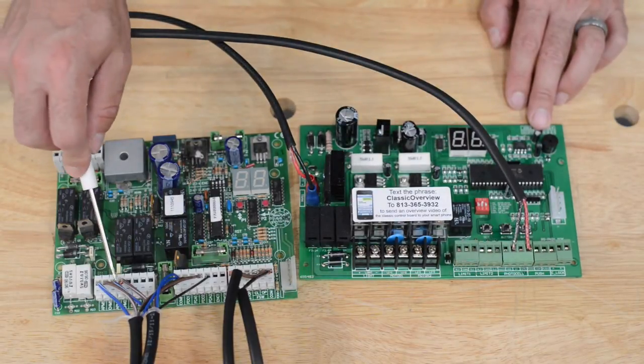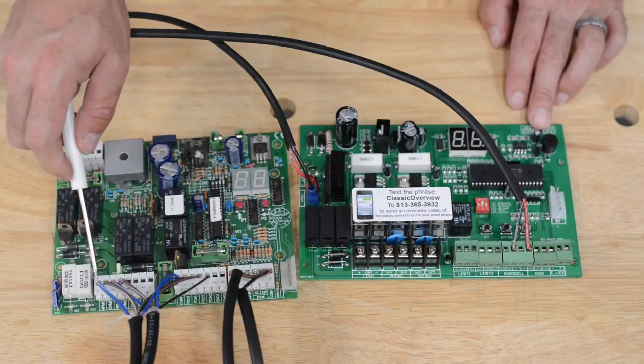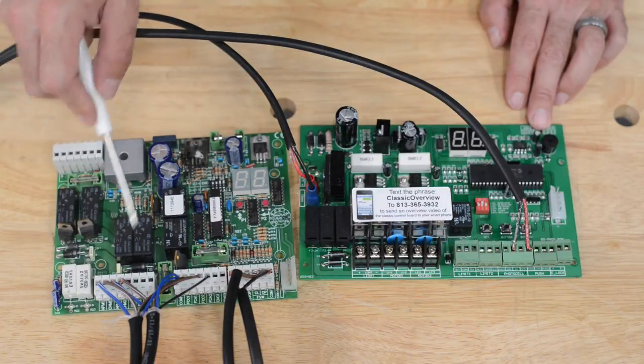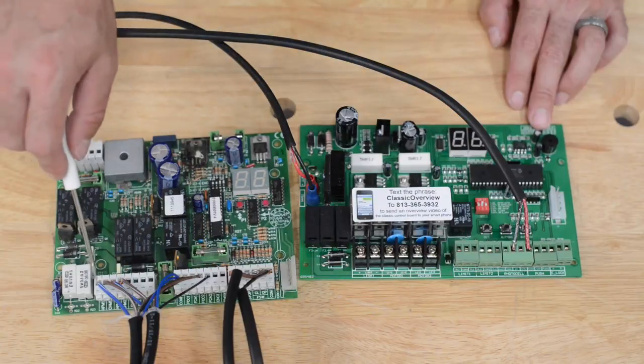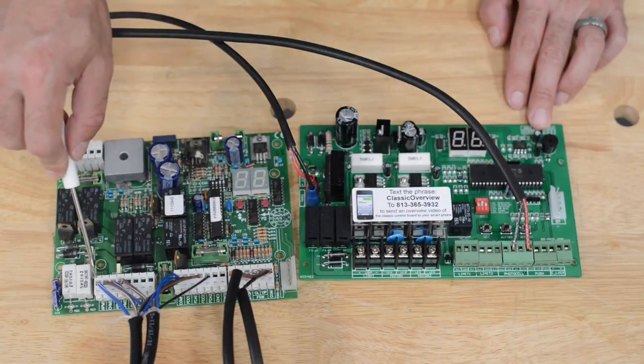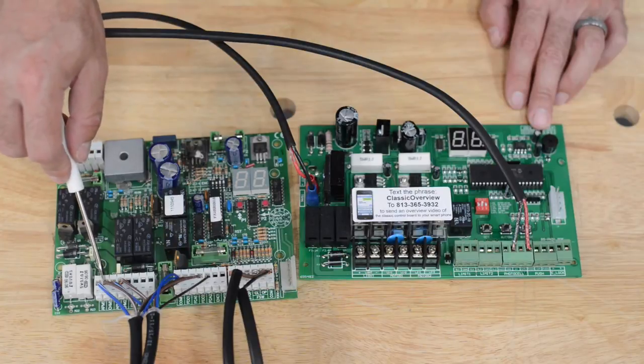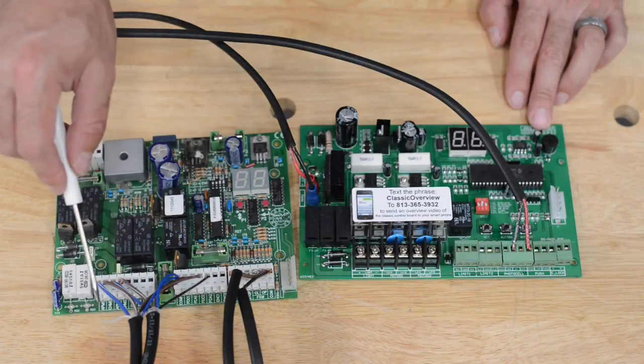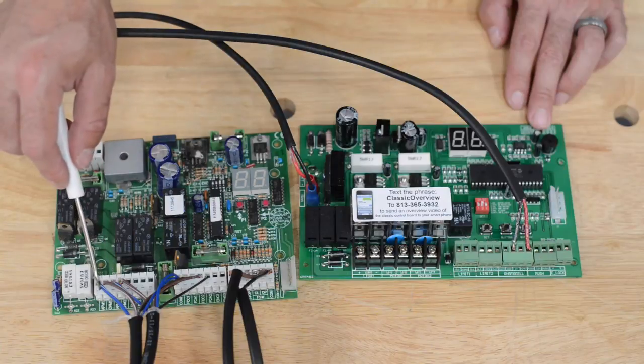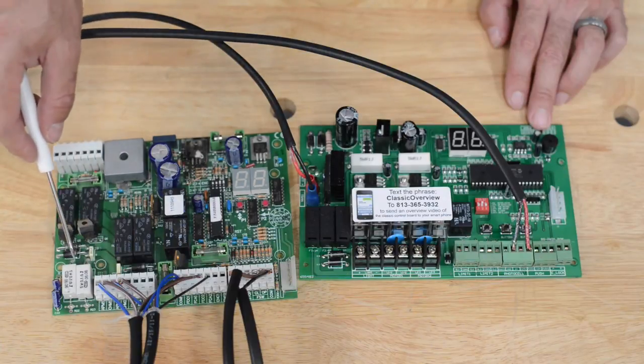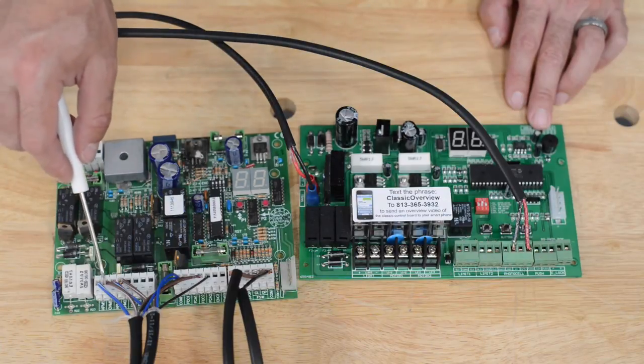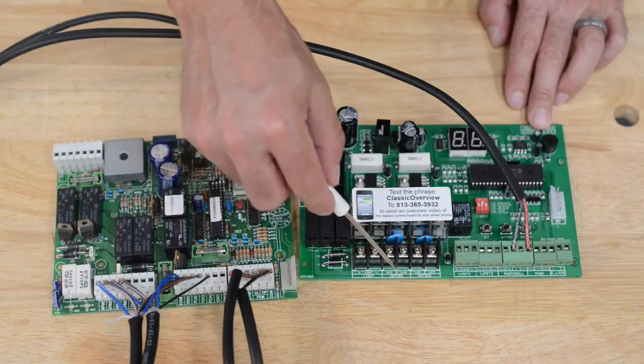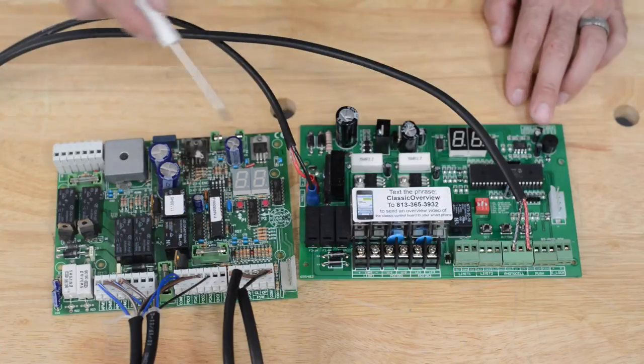We're now going to move to the CN2 block. These first four terminals are the power leads for the operator arms. The APM1 and CHM1 have a large blue and large brown. On newer versions, you might have been supplied wire that was red and black instead of blue and brown. We're going to take these wires out and move them to motor one, L1-1 and L1-2.